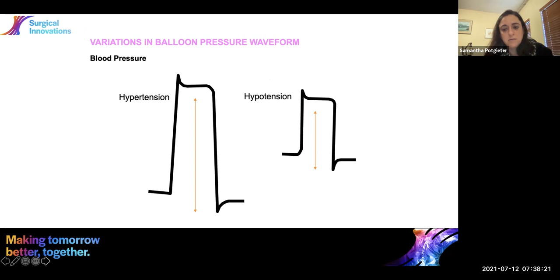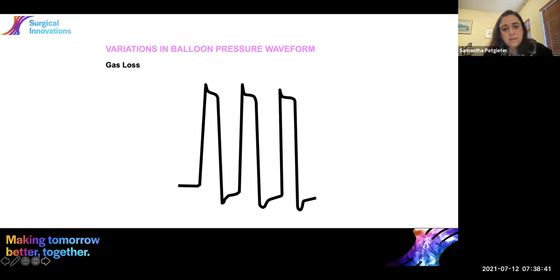Right, gas loss would typically be maybe something wrong with the actual catheter, or you may even have a catheter leak. You can see you've got a reduction coming along here. That's something that you can observe and address. We'll go through that now in terms of your troubleshooting. Kink in your catheter. We see this from time to time, more in an academic sector where the positioning of the catheter isn't correct or where the catheter has kinked.